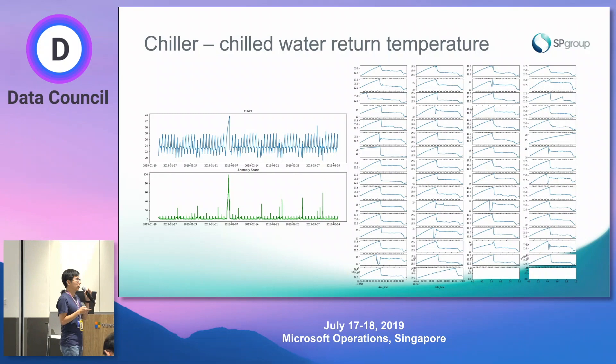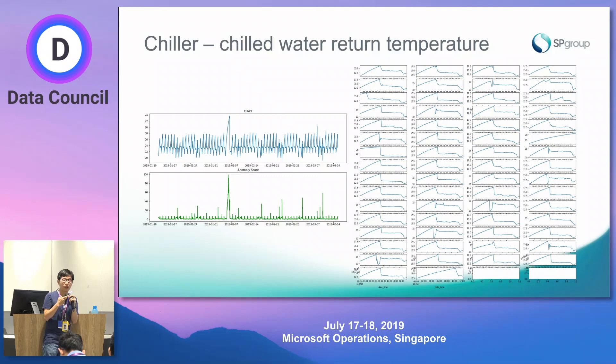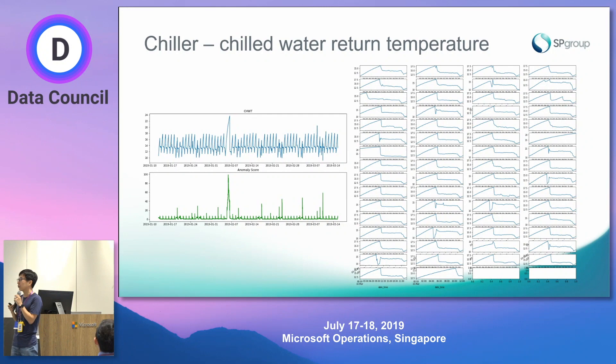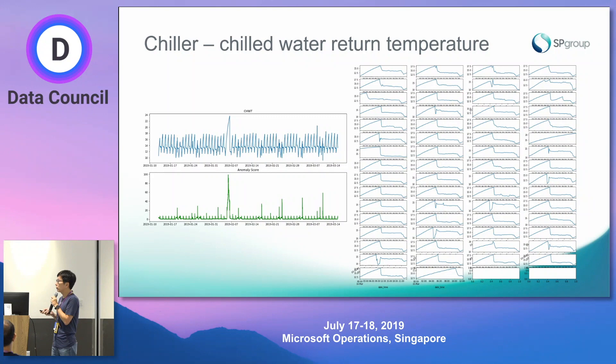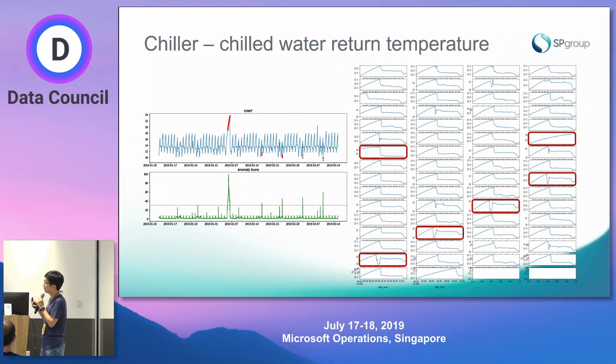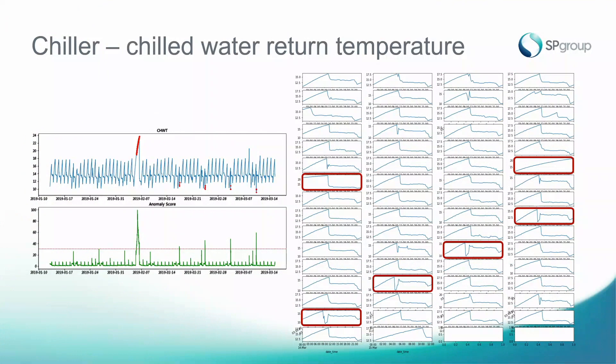This is another IoT time series about the chilled water return temperature from a chiller, with a 15-minute sampling rate and strong sampling irregularity — the misalignment I mentioned. Our solution handles this irregularity well. It successfully detects very obvious anomalies and also detects a misoperation pattern: in the morning the chilled water temperature drops significantly and then comes back, which is unusual compared to other days where the temperature goes up and immediately returns to the normal range.